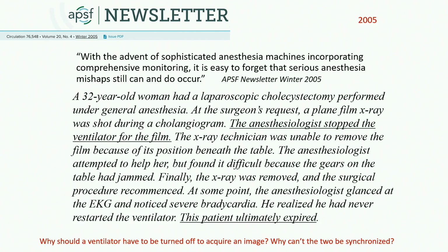Now, this is a problem that's quite rare, but you have to ask yourself, why do we turn off a ventilator to get an x-ray? Those of you who've been involved in photography and other things, you synchronize things, right? You don't turn one off and hope you turn it back on. And for those of you who, like me, are anesthesiologists, or if you work in environments where, say, there are interventional procedures and radiology, neurosurgery, you turn off the ventilator all the time and rush away and rush back.